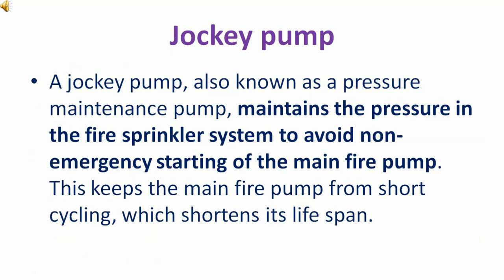Jockey pump. A jockey pump, also known as a pressure maintenance pump, maintains the pressure in the fire sprinkler system to avoid non-emergency starting of the main fire pump. This keeps the main fire pump from short cycling, which shortens its life span.